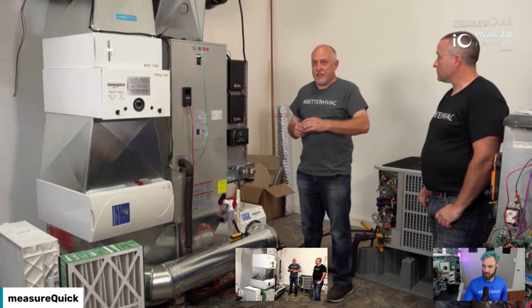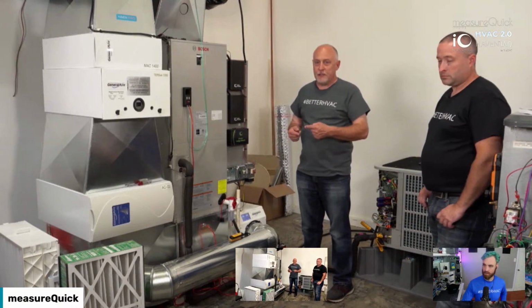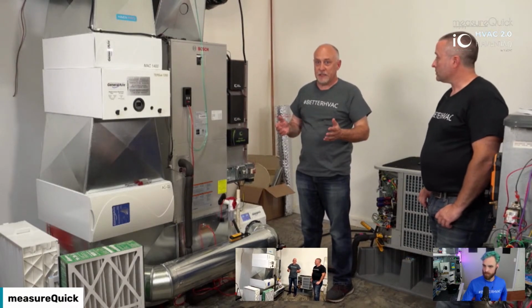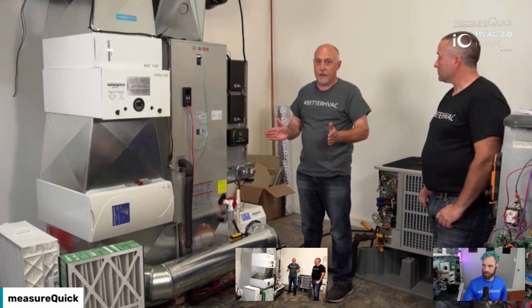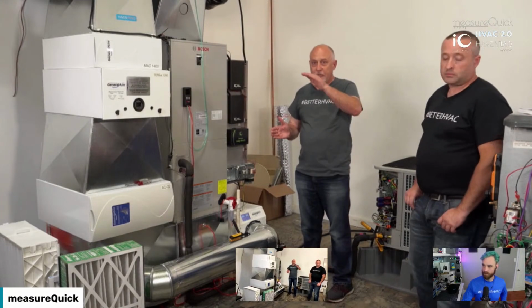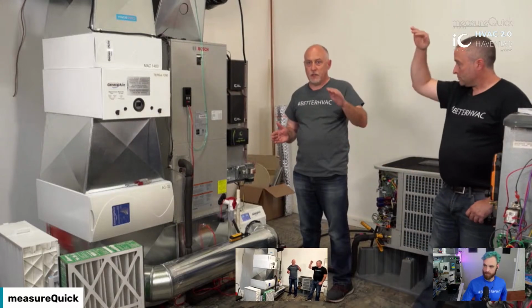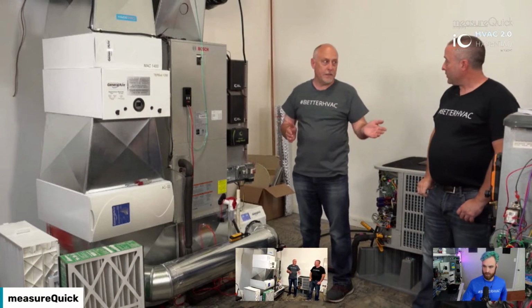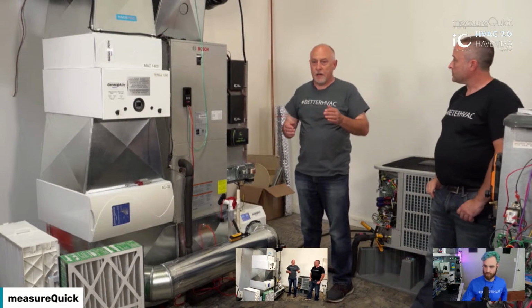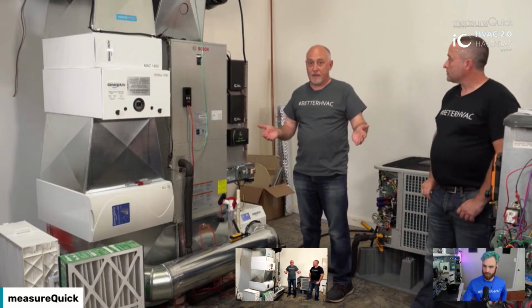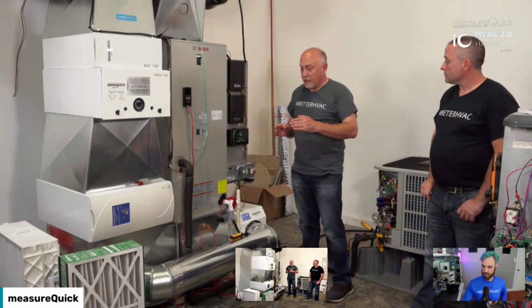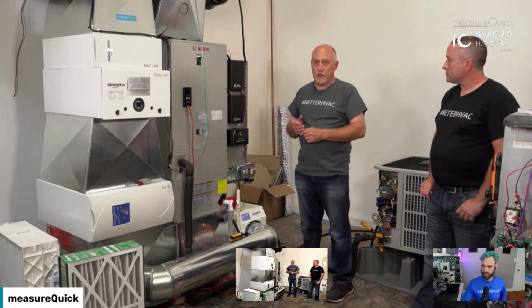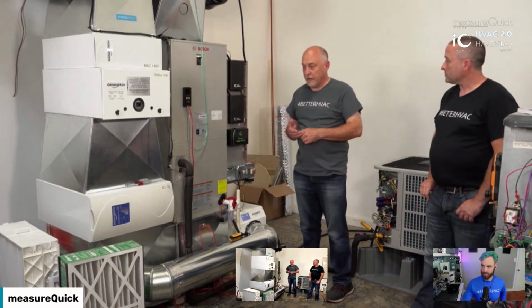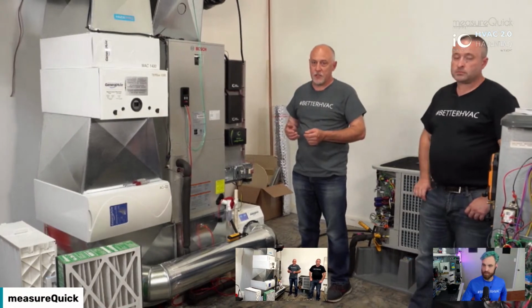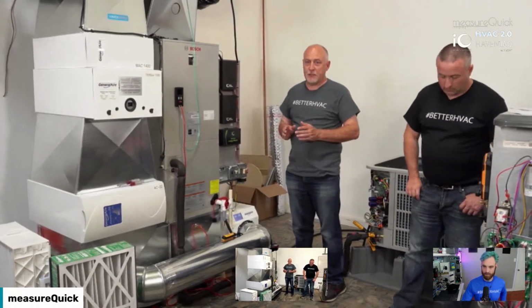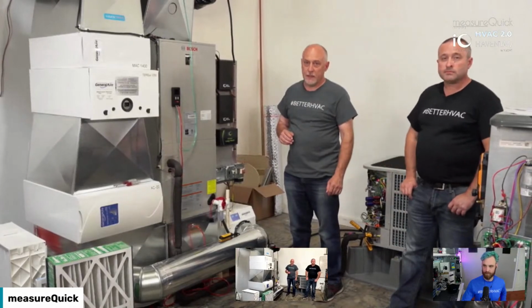So it's really interesting as we're seeing things start to operate, things happening that we didn't expect to see just from the get-go. Like when we have a huge rise in humidity, we're seeing a large rise in our total TVOCs. And the reason we're seeing that is because when things get wet, they tend to outgas. So we're trying to figure out a balance between ventilation and filtration and conditioning the air. So there's a lot of interesting data and some interesting challenges as we're going through this.